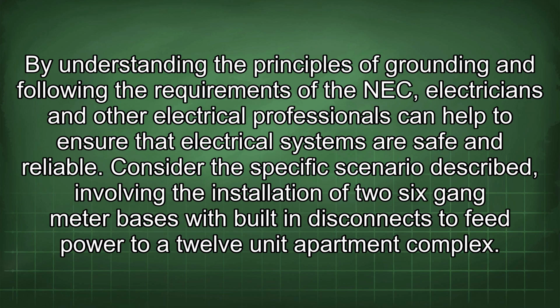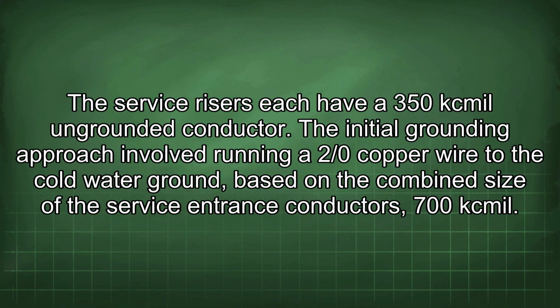Consider the specific scenario described, involving the installation of two six gang meter bases with built-in disconnects to feed power to a 12-unit apartment complex. The service risers each have a 350 kcmil ungrounded conductor. The initial grounding approach involved running a 2/0 copper wire to the cold water ground, based on the combined size of the service entrance conductors, 700 kcmil.